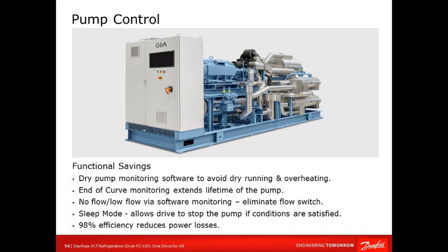For the pumps, obviously we're trying to have a stable flow and pressure, and with the FC-103 we can operate with a direct signal to the drive from the controller, 4-20 milliamp, or obviously, if in the process, with field bus. So again, the flexibility is we can either do a lot of the controlling built into the drive, or just be waiting, receiving the signal from a controller, for example.